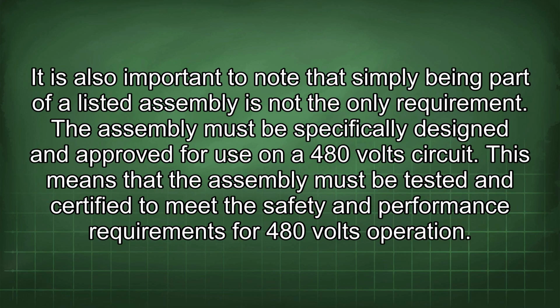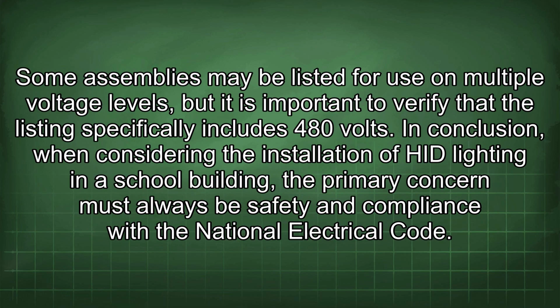It is also important to note that simply being part of a listed assembly is not the only requirement. The assembly must be specifically designed and approved for use on a 480-volt circuit. This means that the assembly must be tested and certified to meet the safety and performance requirements for 480-volt operation. Some assemblies may be listed for use on multiple voltage levels, but it is important to verify that the listing specifically includes 480 volts.